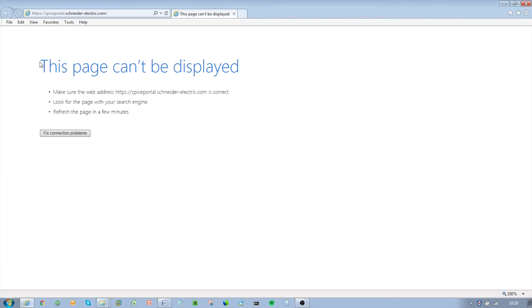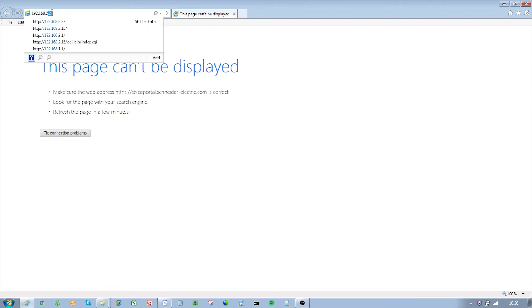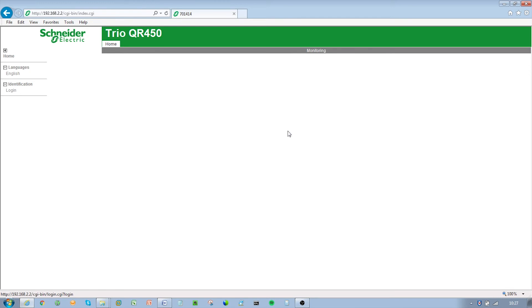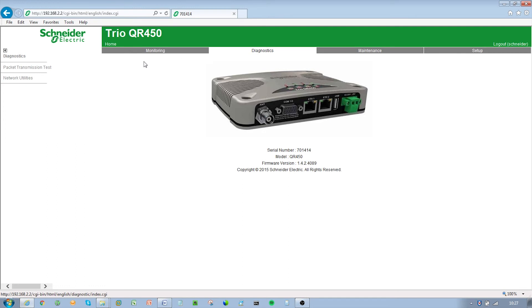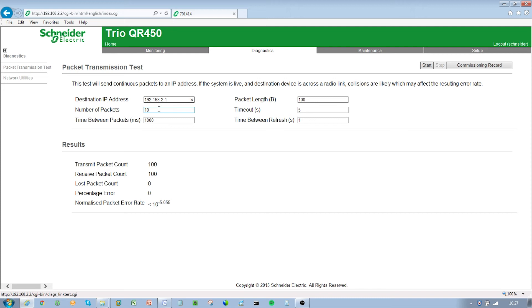For testing the communications, wait for the TrioQ data radio to restart and navigate to the new IP address. You will need to log in. Browse to the packet transmission test section of the WUI by clicking on Diagnostics and then Packet Transmission Test. Enter the IP address of the entry point radio and set the number of packets to 1000. Hit the Start button on top right.